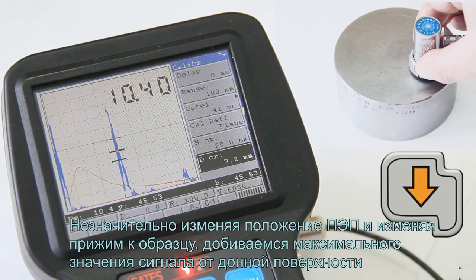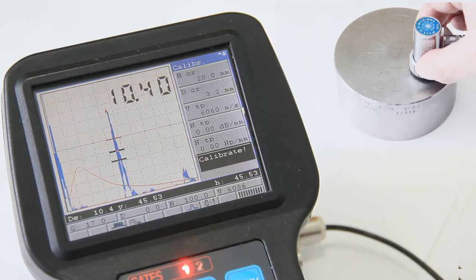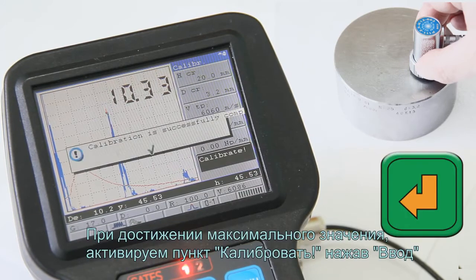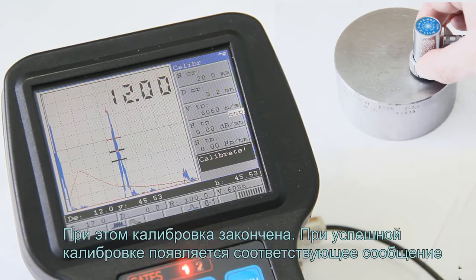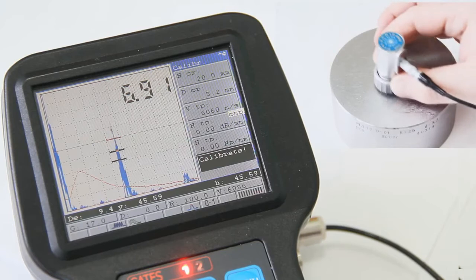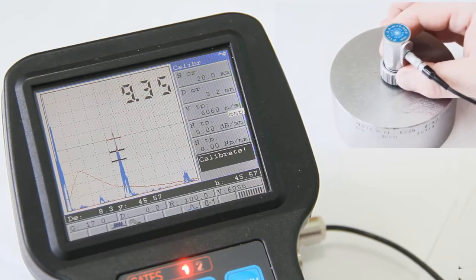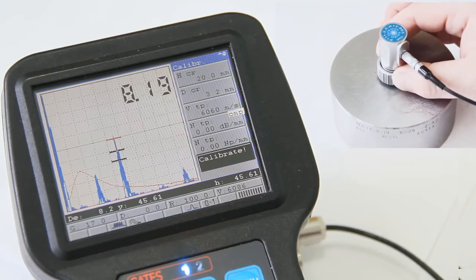Slightly change the probe position and change the probe pressure to the block to achieve the maximum backwall echo. Having achieved the maximum value, activate the calibrate item by pressing the Enter key. The calibration is finished. In case successful calibration, the following inscription is appeared.